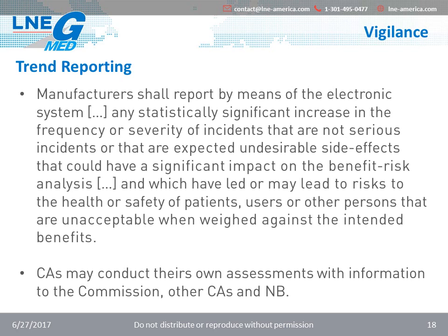The manufacturer shall also specify how he manages these incidents and the methodology used for determining any statistically significant increase in the frequency or severity of such incidents, as well as the observation period in the post-market surveillance plan. Competent authorities may assess this data and require the manufacturer to take action. In this case, the competent authority shall inform the Commission, the other competent authorities, and the notified body that issued the certificate of the results of such assessment and adopted measures.